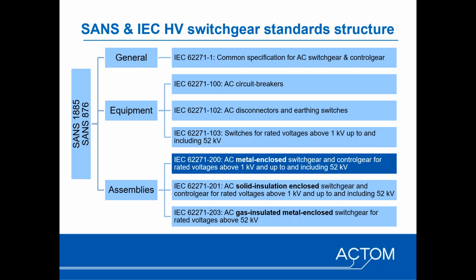Then in the 100 series, you've got switching devices, for example, circuit breakers, disconnectors, commonly called isolators, but the correct term being disconnectors, and earthing switches, covered by 102. And then 62271-103 would cover switches, switch disconnectors, sometimes referred to as load break switches, in the medium voltage range up to 52 kV. Of course, there's many other types in the 100 series.